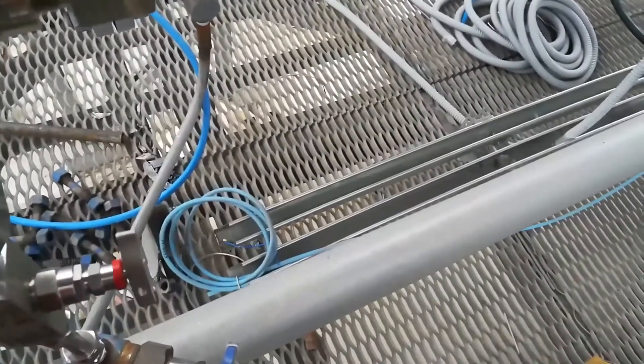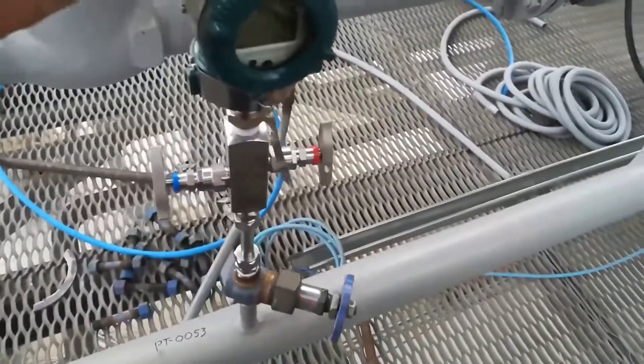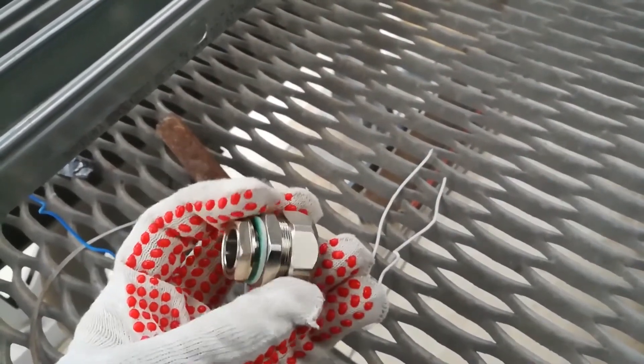A strong armored shielded cable with a cross section of one square millimeter will come from that tray over there. Here I have already drilled a hole with a special crown with a diameter of 20 millimeters, and the cable will pass through this coupling.